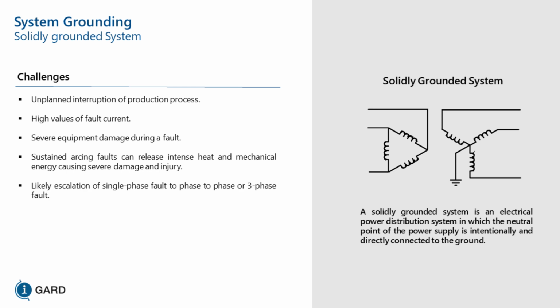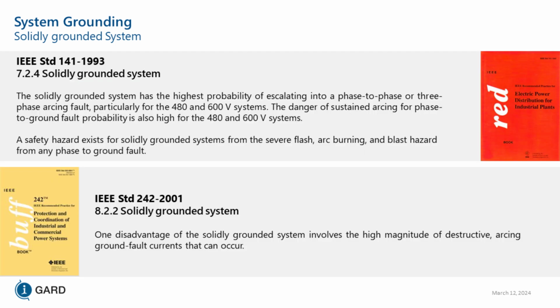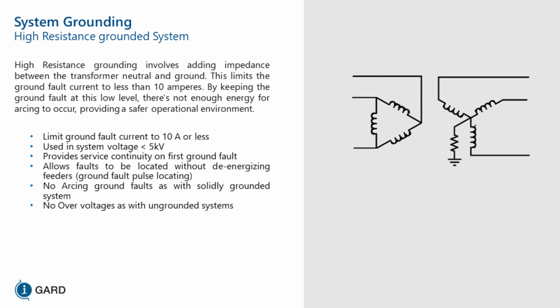So let me explain this a bit. Remember, Dunki-Jacobs said that 95% of all faults begin as single-phase to ground faults. So in a solidly grounded system, because faults begin as single-phase to ground faults, you have a high probability of a single-phase to ground fault escalating to a phase-to-phase and 3-phase fault and an arc flash event. Whereas in the ungrounded system, you didn't have that problem, you had other problems. So again, the Red Book and the Buff Book all say that solidly grounded systems have high magnitude destructive current and danger of sustaining arc flash due to fault probability.